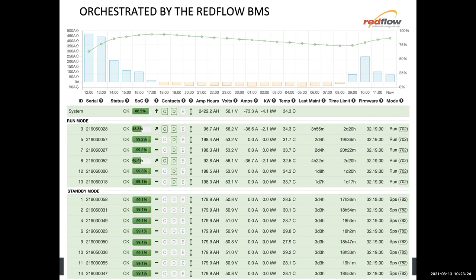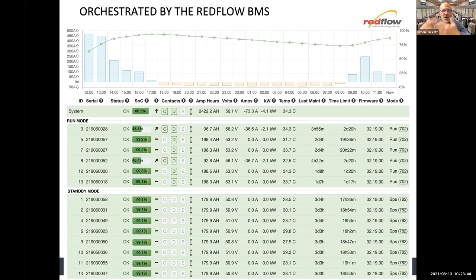Then the next day, hopefully there's a bit more sunshine, and those batteries get recharged again and go back on standby ready for next time. The benefit is that batteries on standby have no self-discharge and no internal self-degradation, so you get a lot more energy efficiency out of these machines by actually turning them off. You can have this hybrid structure where some are on standby, some are running, and you can modify that proportion over time. The battery management system I designed orchestrates all of that process.